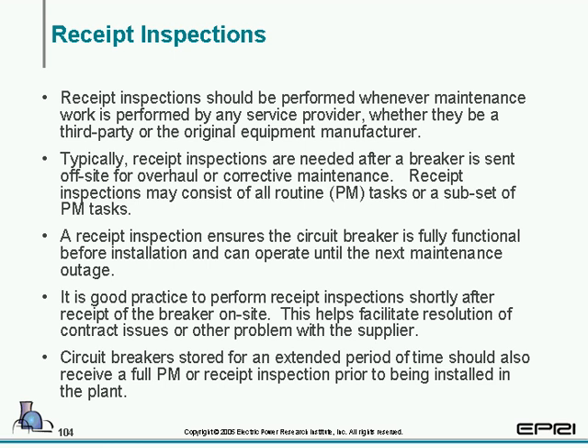It's a good practice to perform these shortly after the breaker is received on site. If you ship your breakers out for overhaul or maybe corrective maintenance, as soon as they get back to site, you should check them over. As a side note, this also helps facilitate resolution of any contract issues if you should run into any.